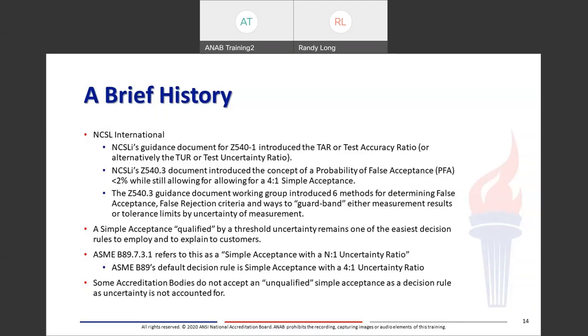In the Z540.3 document, which came out in 2006, a concept called probability of false acceptance was introduced. They were trying to reduce it to less than 2% while still allowing for the 4-to-1 simple acceptance. The Z540.3 guidance document working group introduced six different methods for determining false acceptance and false rejection criteria, and ways to guard band either measurement results or tolerance limits by that uncertainty in measurement. There are actually several more methods out there now. A simple acceptance qualified by a threshold of uncertainty remains one of the easiest decision rules to employ and to explain to your customers.